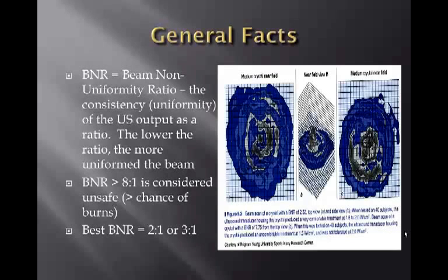BNR is the beam non-uniformity ratio. This is the consistency or uniformity of the ultrasound output as a ratio. The lower the ratio, the more uniform the beam. If the BNR is greater than an 8 to 1 ratio, it is considered unsafe and it's going to increase your chances of burns. The best BNR found on machines is a 2 to 1 or a 3 to 1, so the importance of this is decreasing the risk of burns.